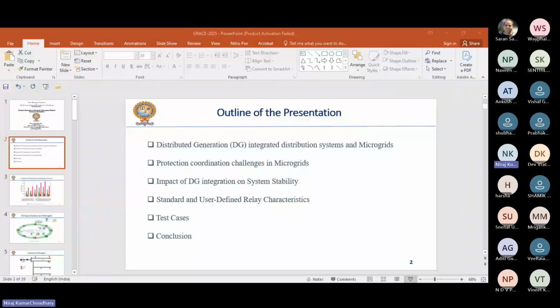So different standard relay characteristics are there, if you look at the IEC 60255 characteristics or the IEEE standards. Some relays are also modified, named as user defined relays. They are modified as per the requirement of the utility system, meaning depending upon the load requirement or the type of DG connected to the system, the characteristics of the relays are modified. We will see the application of such relays in the coming slides.